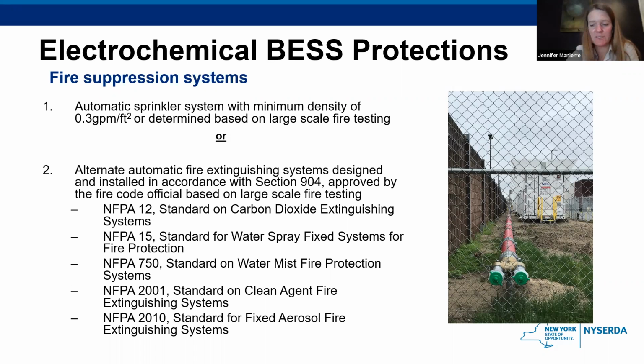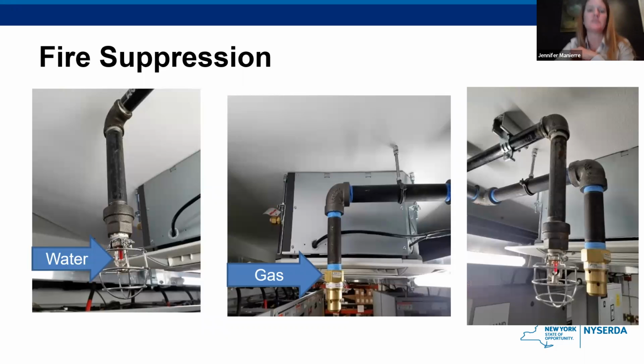There are some fire suppression system requirements in the code. They either need to have an automatic sprinkler with a minimum density of 0.3 gallons per minute per square foot, or a rate of flow as determined by large scale fire testing. Or there is a whole slew of other options as well that are not just automatic sprinkler systems. You can see them, different clean agents and things like that. Okay, so this slide shows some of the different fire suppression systems you might see: water, perhaps gas, perhaps both.